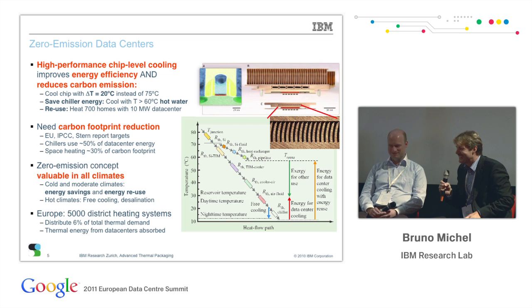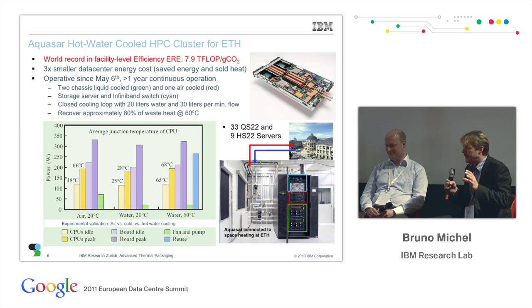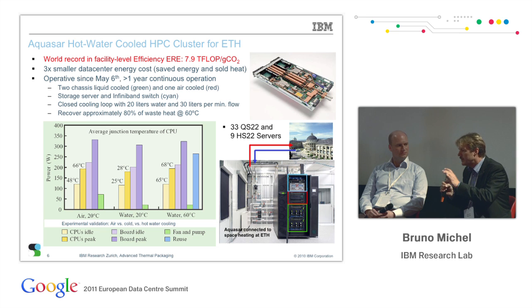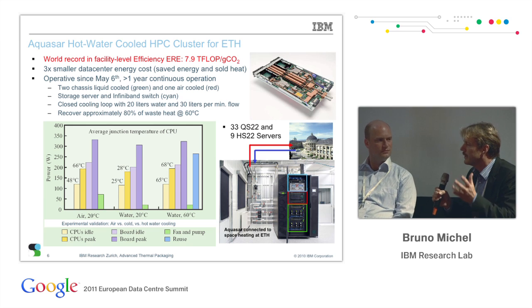So now, next slide. So we compared the design, an air-cooled design, with a high-performance cold water-cooled design and a hot water-cooled design. So the cold water design, high-performance cooling, reduces the processor temperature by 40 degrees compared to what it is in an air-cooled version. That reduces the energy consumption. That's good. It reduces energy consumption with constant fan speed at about 5%. That's the transistor physics. Now, if we increase the temperature back to the temperature it was in the air-cooled blade, we have the same processor temperature, 68 degrees, 60 degree coolant input, 8 degrees delta only between the coolant and the transistor. We have the same energy spent as in the air-cooled version, but we make a large fraction reusable.